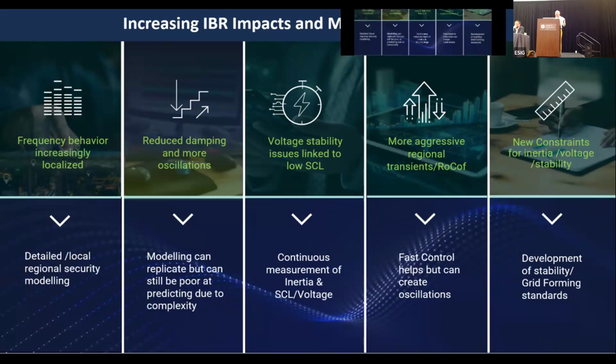Second thing we see globally is significantly reduced damping, obviously. Quite a lot of people talk about this in terms of plant retirement, but actually the main thing is reduced plant operation. So if that plant is not running, you're not getting the synchronous damping from it, and you see a fundamental change in the behavior of the system. That's really important. North America is really the capital of studies on oscillations and the behavior of oscillations on the system. As you reduce damping, a lot of those traditional forced oscillations we're used to are still there when people make a mistake or code their system wrong. But what we see much more of in places like the UK and Australia is effectively the arrival of ambient oscillations, where you've got lots of active controllers all talking to each other.